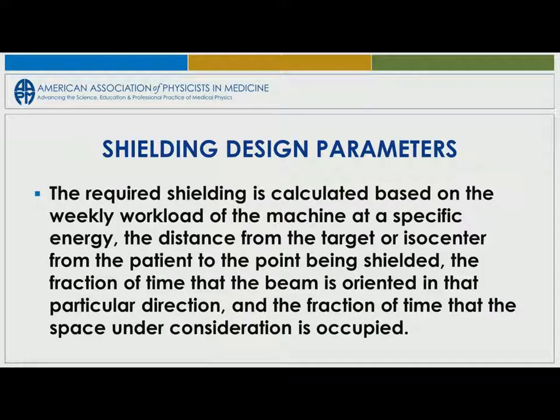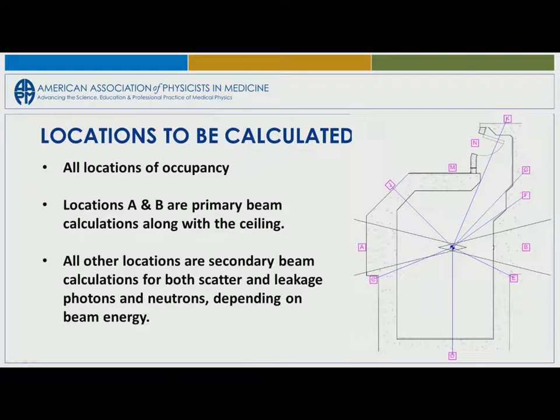So what would go into calculating these radiation shielding requirements? The weekly workload of the machine at a specific energy. We're going to go through some examples here in a little while of how to specify a workload. The distance from the target or isocenter from the patient to the point being shielded. The fraction of time that the beam is oriented in that particular direction. And the fraction of time that the space under consideration is occupied. Again, I think you've probably heard those, but that's a good SAM's question.